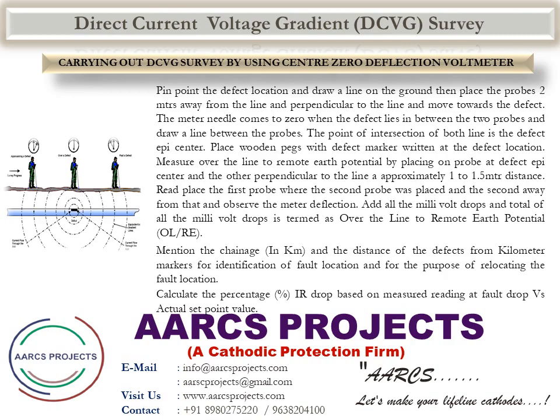Place wooden pegs with a defect marker written at the defect location. Measure over the line to remote earth potential by placing one probe at the defect epicenter and the other perpendicular to the line, approximately one to one and a half meters distance. Replace the first probe where the second probe was placed and move the second further away, observing the meter deflection. Add all the millivolt drops — the total of all millivolt drops is termed as over-the-line to remote earth potential.